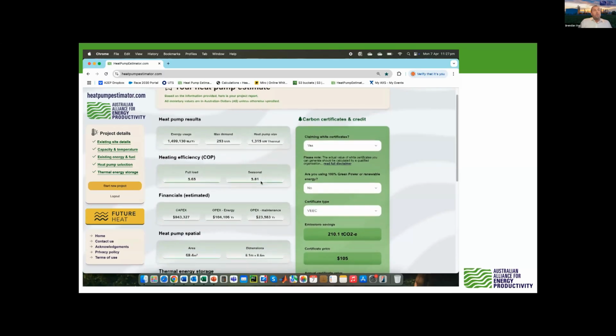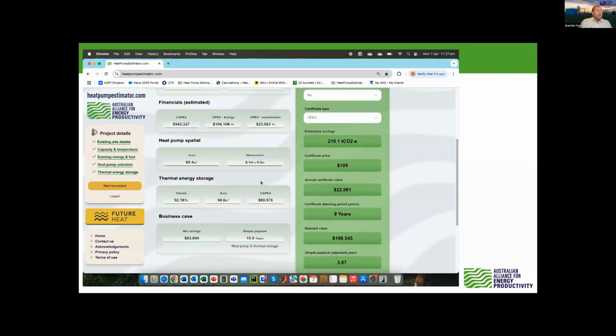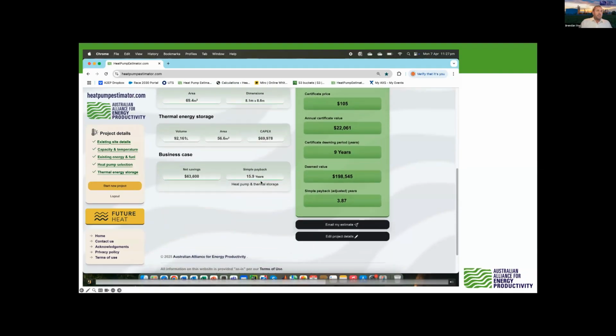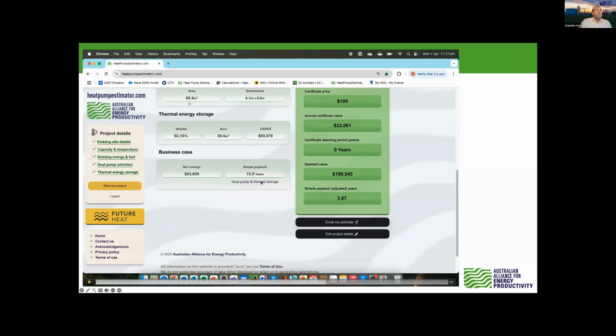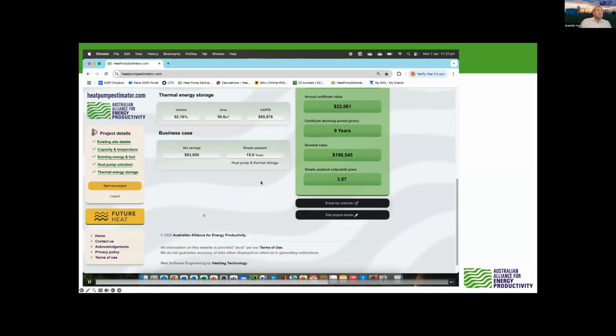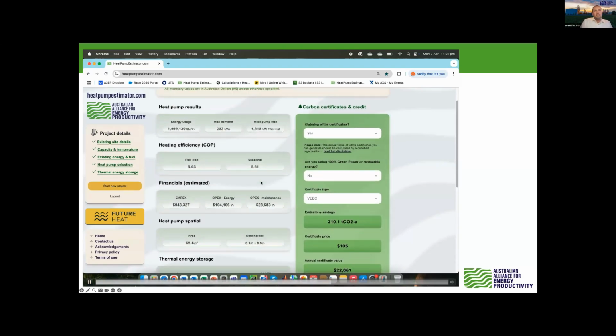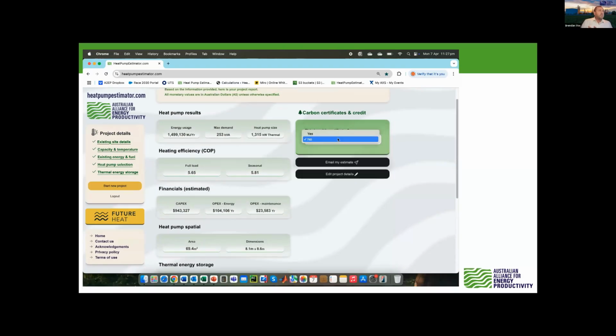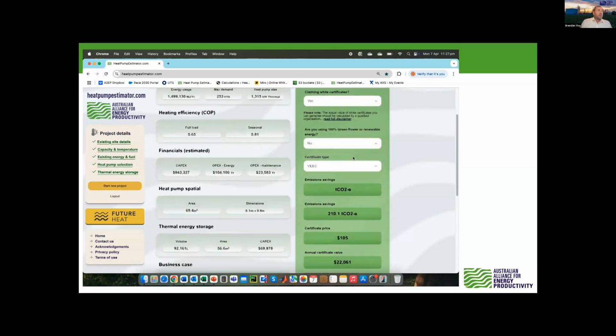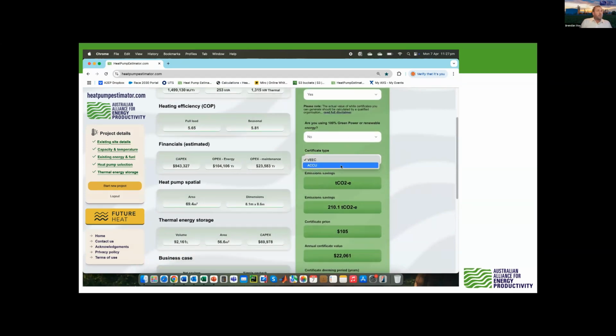Now we pause on our output and we can see we've got our energy usage, we've got our heat pump size, we've got our seasonal COPs, and some other really cool things here. We have estimated dimensions for what the heat pump will actually take up. We have a thermal storage calculated number, and we have an area for that as well, and we have a simple payback. It doesn't start wonderful, starts at 15.9 years, but that's kind of normal, which is where the certificates come in. And we say, okay, do you want to claim certificates like we talked about before? So you've got VEECs, ACCUs, ESCs all built in. They're a 3-month rolling average price. We can update those as we go.